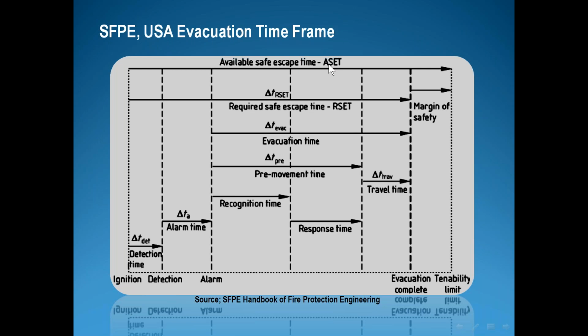ASET, the available safe egress time, is based on the architect's design. And this is the required time, which we need to save. Normally, we define this time before the people leave the building, according to tenability. What is the tenability? The tenability criteria are a group of parameters that shall be studied together, that define clearly the indoor environmental quality of the building or the zone affected by fire inside the building.